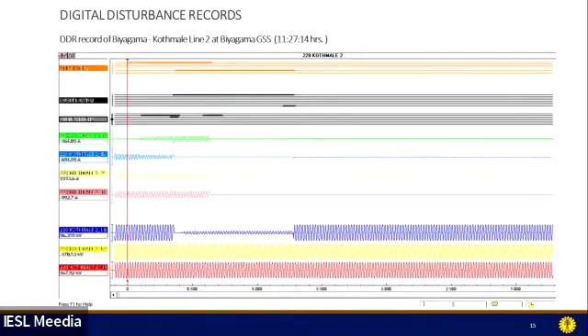This is from the digital disturbance record. So initially, other than the B phase, the other two phase currents flow as earlier. But after about 280 milliseconds, the line got tripped from Kothmale end, and transfer of power stops at that point. However, after about 0.89 seconds, from Biyagama end, the line got auto-reclosed and the Biyagama end breaker closed.